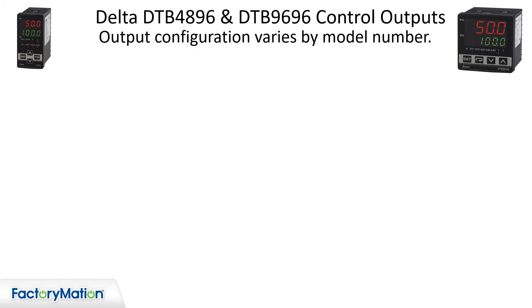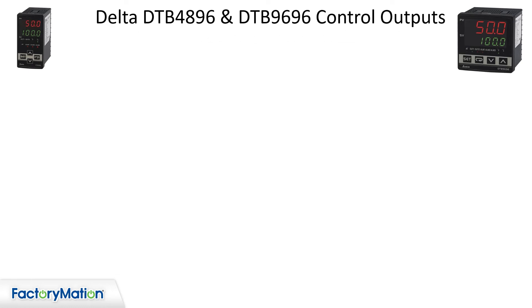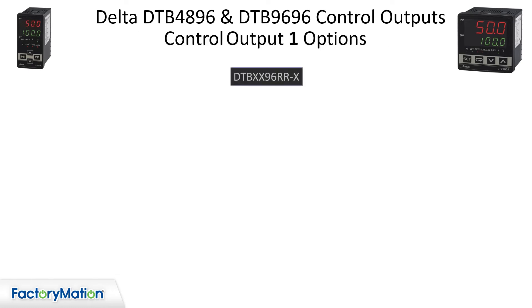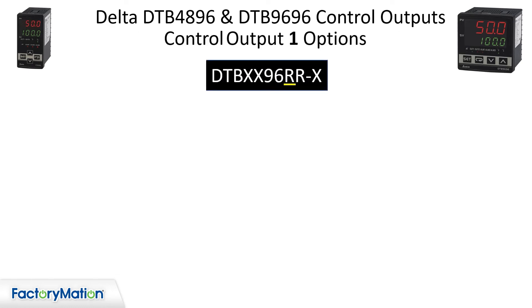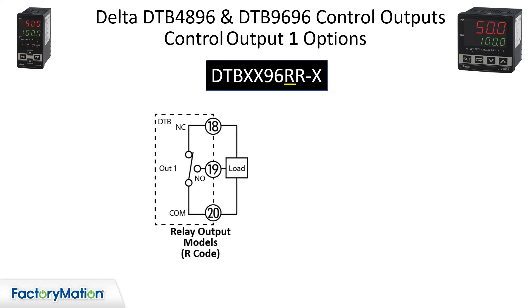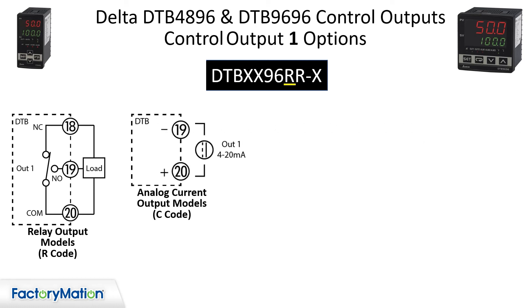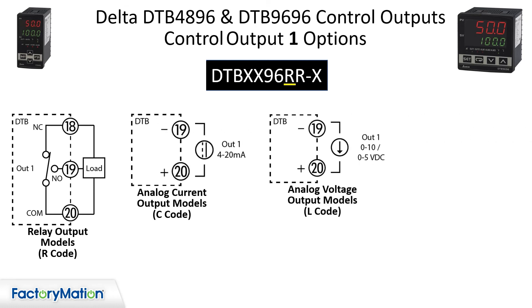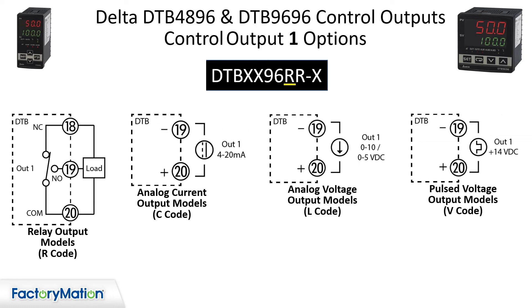Output configuration varies by model number. The first alpha character in the model number designates Output 1. Output 1 can be a relay, analog current, analog voltage, or a 14-volt DC pulse output to drive a solid state relay.